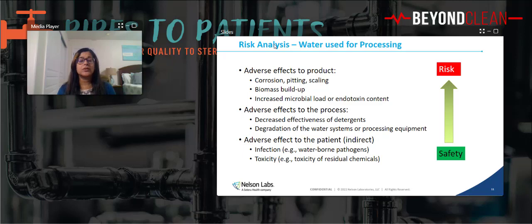Toxicity of residual chemicals. If you're not using the right water, the residuals are still there, and it can cause burns. It can cause irritation, and we've seen that. We've seen many examples of that during other conferences, where residual chemicals are sometimes left because we didn't use the right water to clean them off.